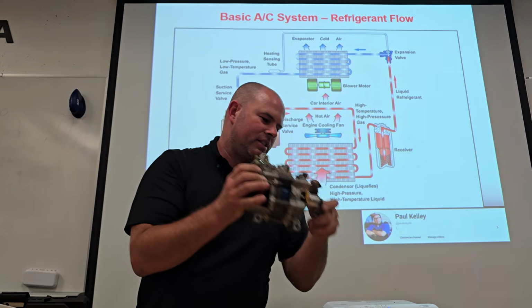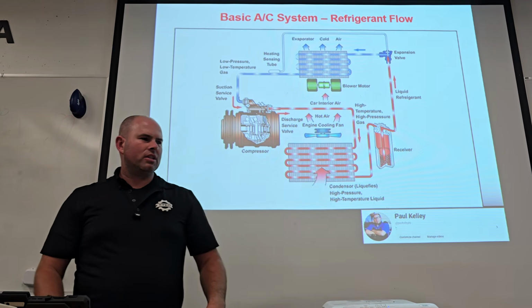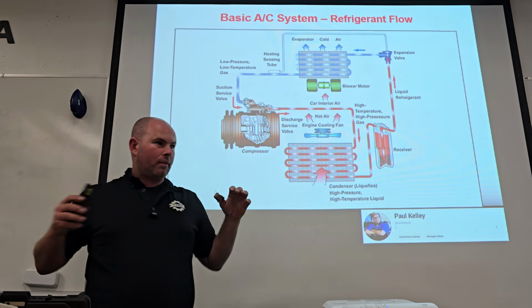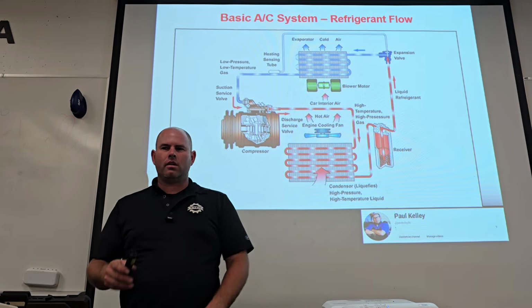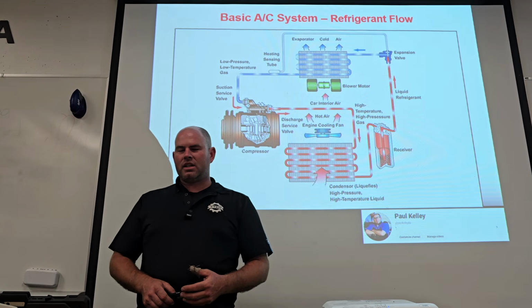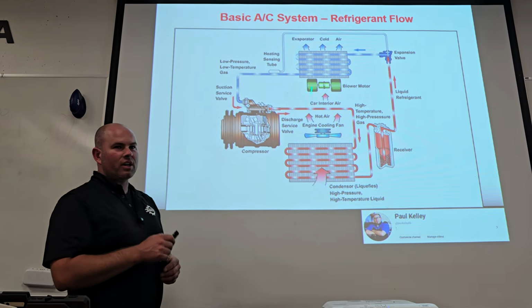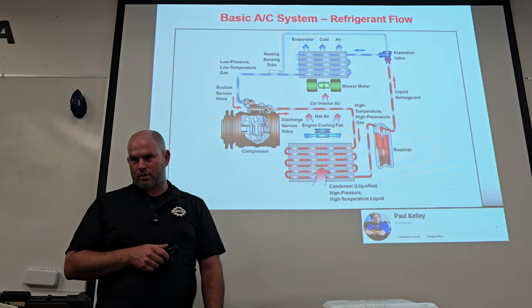All right, but you can see this. If we were to send liquid refrigerant into that compressor, you know, liquid's incompressible, right? It's going to try to pull liquid in and try to compress it, and it's not going to be happy. Make sense? So the thing I like to remember is near the compressor, this is always vapor over here. The compressor doesn't process liquids. You're going to blow a compressor up if it's liquid.